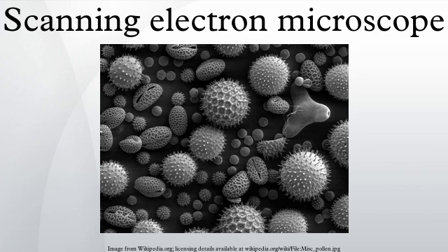Resolution of the SEM. The spatial resolution of the SEM depends on the size of the electron spot, which in turn depends on both the wavelength of the electrons and the electron optical system that produces the scanning beam. The resolution is also limited by the size of the interaction volume, the volume of specimen material that interacts with the electron beam.